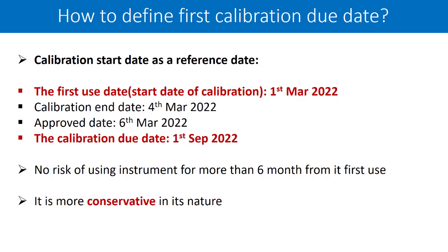Therefore, I will say that my first calibration due date is going to be 1st September 2022. And again, from this 1st September, I will consider another 6 months, then another 6 months, and so on. Understanding the first calibration due date is very important. This is my approach, based on the nature of the method.